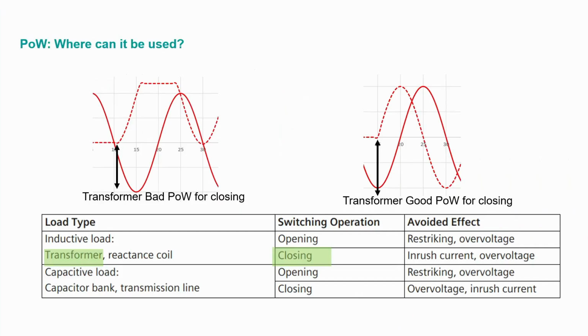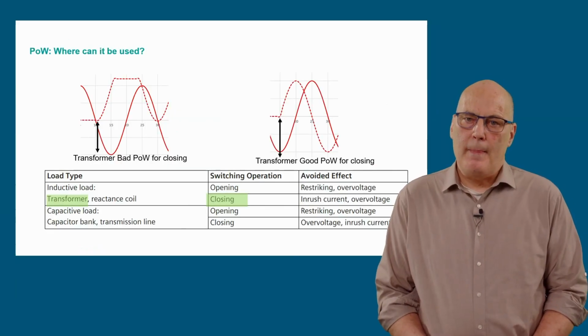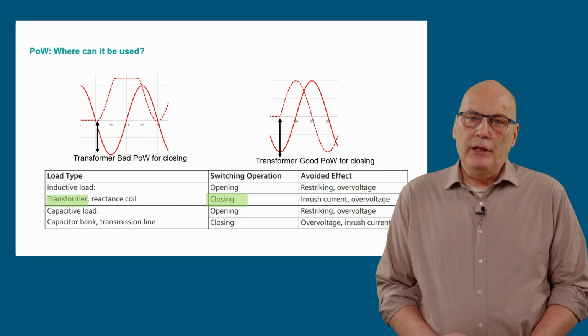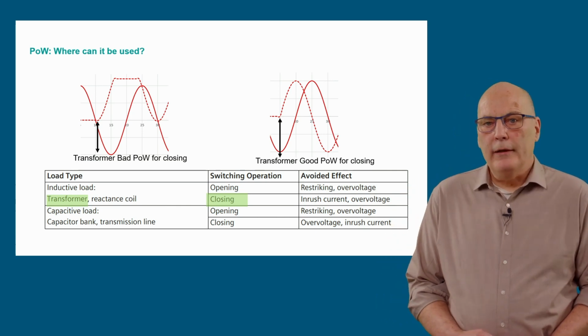Where can point-on-wave switching be used? Is it only on capacitor banks as shown on the previous slide? And the answer is no. Point-on-wave switching can be used almost always, as transients are generated by every closure and opening of circuit breakers. The situations that are listed here are of particular interest.